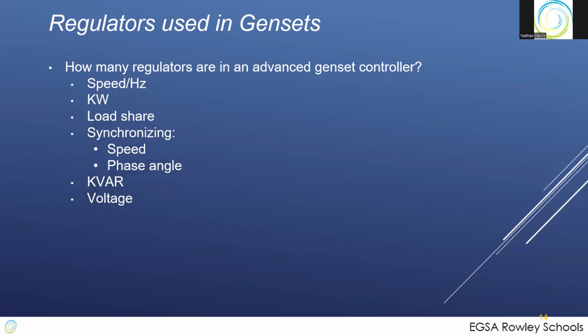Speed, obviously. For a single generator feeding a single load, you regulate speed, which of course is frequency. With that single generator feeding a single load, you'll also have a voltage regulator regulating the voltage. But when you parallel those machines with another one, you have to look at kilowatt. So if you put one generator against the grid, once you close your grid breaker, you normally go to a kilowatt and kilovar regulated system. So kW and kvar regulated once you tie with utility.